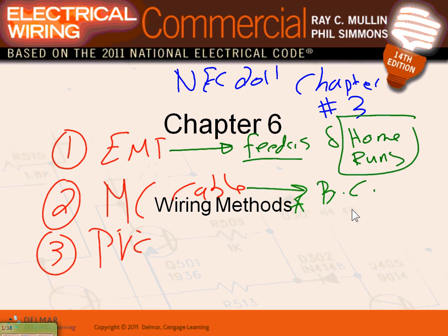And from the same box, I can pull an MC cable right through these blocks and feed the receptacles in the wall too. That would be an easier way. Though EMT conduit might be a better option for anything concealed. Why? Again, future expansion and changes.